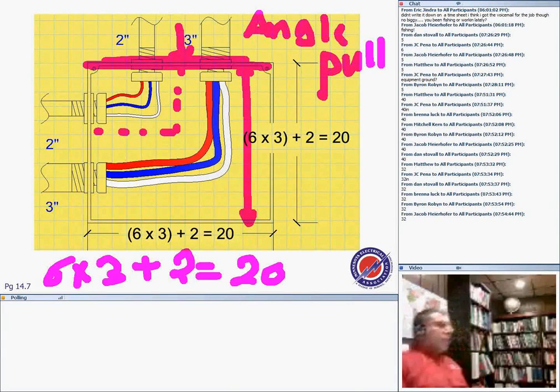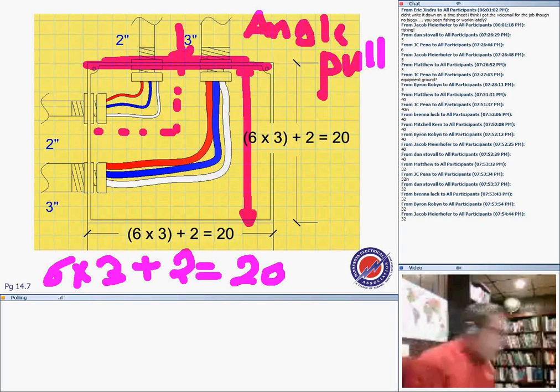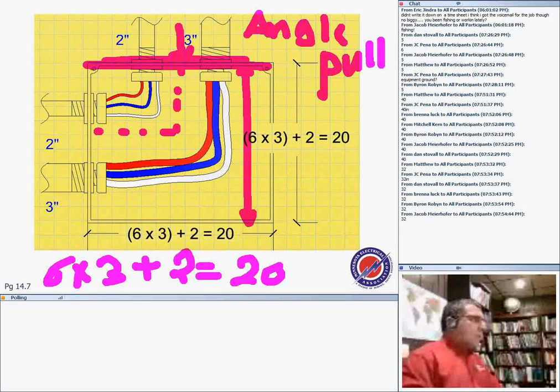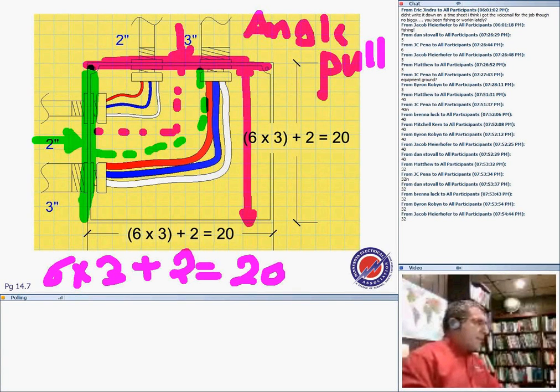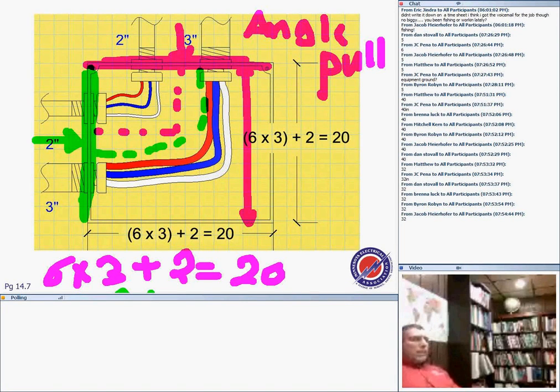Any question how I came up with the height of the box, 20? It comes from the rule, with the conductors coming from the top and going to the left. Now I'm looking at this wall right here, and conductors come in and go the other way. So I'm looking at this wall: 6 times the largest conduit, still 3, plus all the other conduits that enter, and you get another 20. Here's how we came up with the dimension of 20. Any questions?